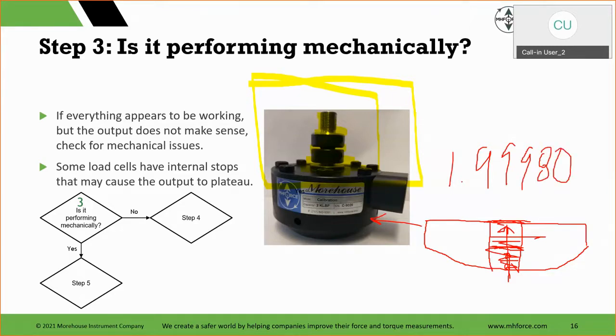In that case, this is a mechanical problem. The other part of it is this threaded adapter here. If we jam this too far down, you won't get this from Morehouse because it's all tested here. Though this is something that we've observed and seen from some other manufacturers. If this is too far threaded down, then it's going to touch that, and there's a way to readjust your threaded adapter. That being said, if this piece right here comes out, it drastically changes the calibration. So the device needs to be recalibrated if you do have a problem where something is bottoming out.